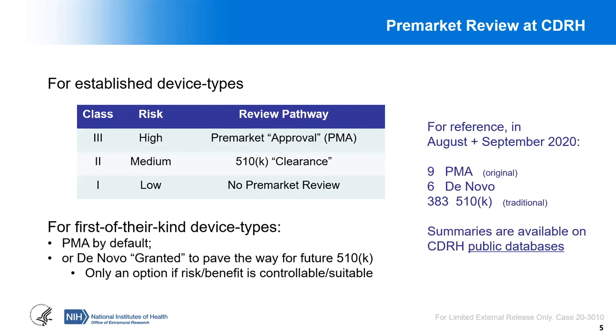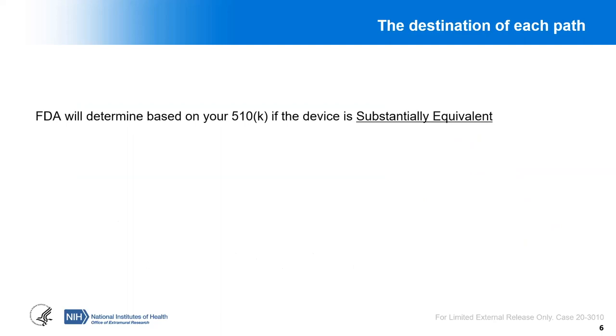I'm pulling these numbers from FDA's website and the CDRH public databases. I'll be showing examples from those throughout the slides. On these public databases, you're able to look up the regulatory decisions made on essentially all products on the market in the U.S. We're going to take a deeper dive into these three pathways — 510K, PMA, and DeNovo — and try to have a better understanding of what these are and when they apply.